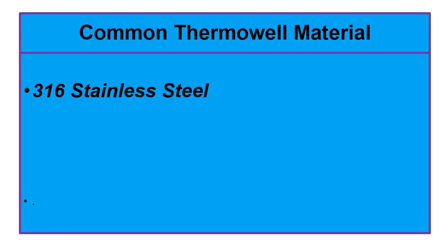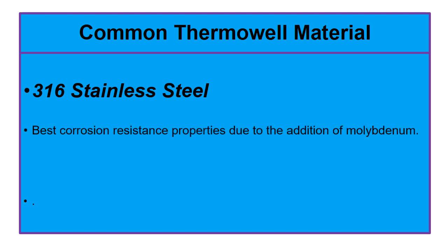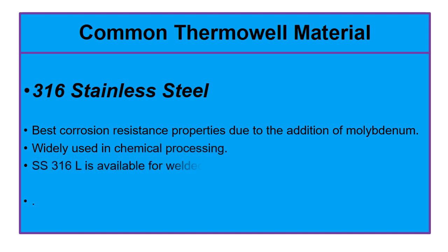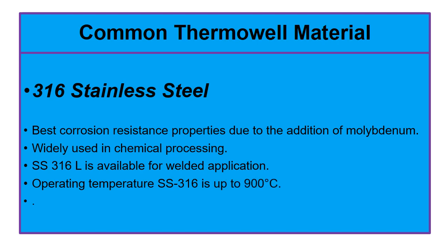SS 316 stainless steel has the best corrosion resistance properties due to the addition of molybdenum. SS 316 is widely used in chemical processing. An SS 316L version is also available for welded applications. The maximum operating temperature of SS 316 is up to 900 degrees centigrade.